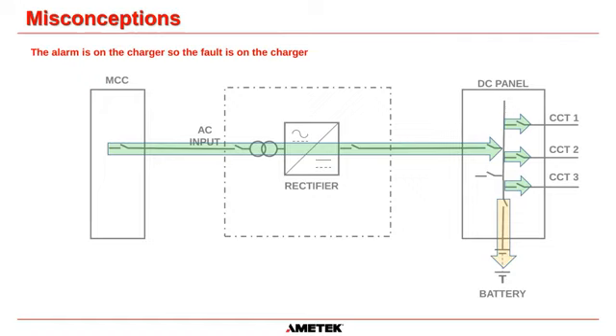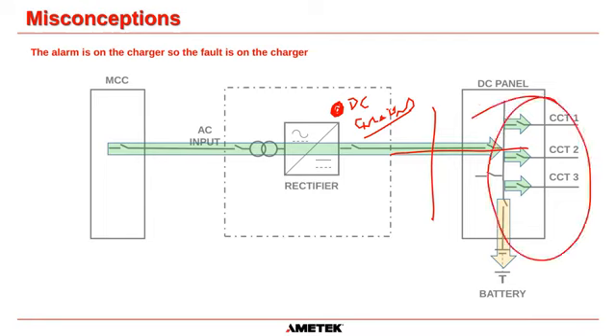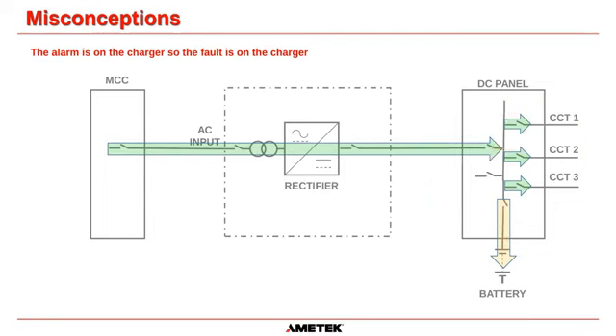Okay, so common misconceptions. The alarm is on the charger, so the fault is on the charger. Well, I think I've discussed that. That is the most common misconception we get, because the red alarm comes on the charger and it says DC ground fault. Everybody says, well, it's on the charger, so the fault must be in the charger. It is so rare that is the case. It's usually always downstream of the charger out here. Such a common misconception. This is just the alarm circuitry. The actual fault is going to be out here 99 out of 100 times. I can't give you 100% on that.